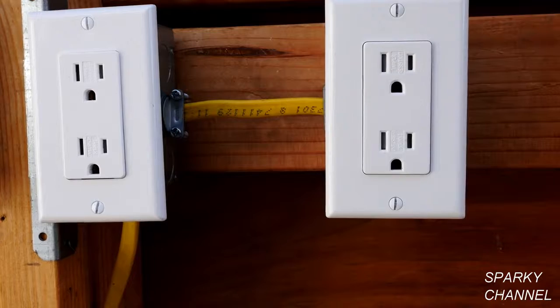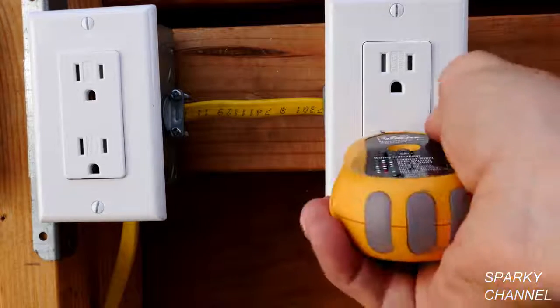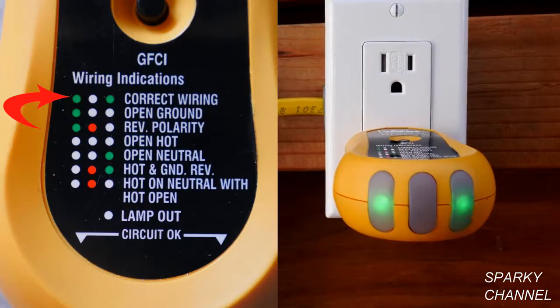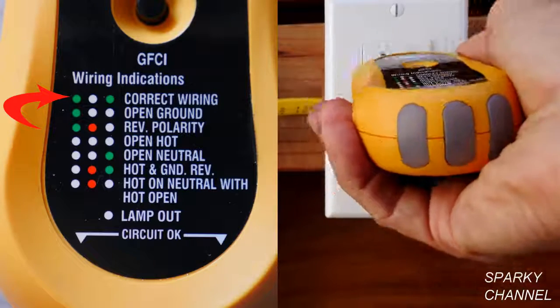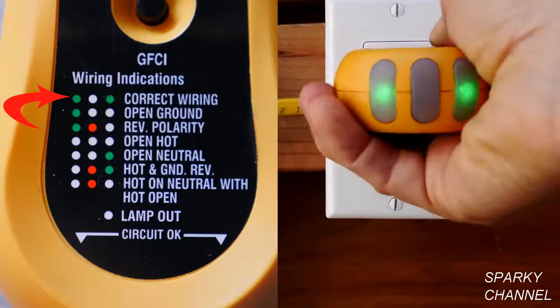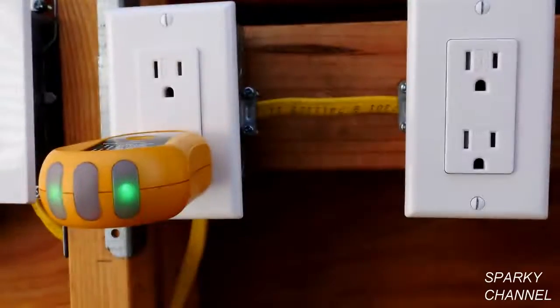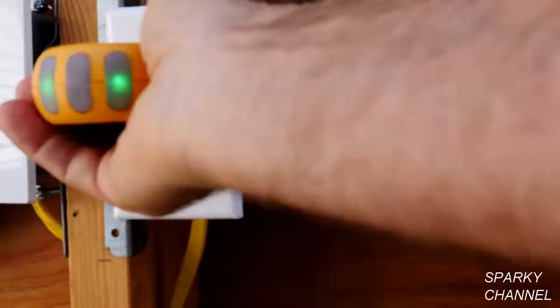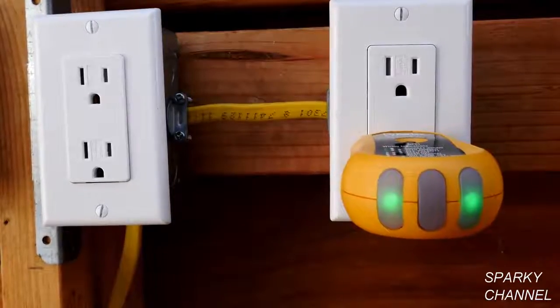Now I've turned the circuit breaker back on. I'm going to plug in my outlet tester to see if we're correctly wired, and we are. So we can test the upper outlet as well, and that's good. And we can test the upstream receptacle, and we see that that one is wired correctly as well. That's how you fix an open ground.